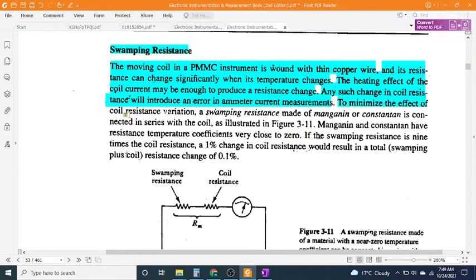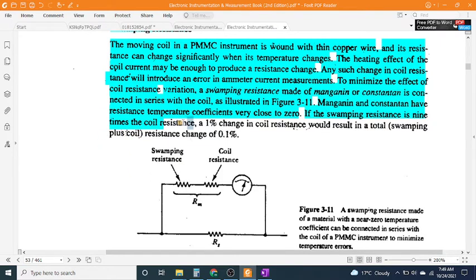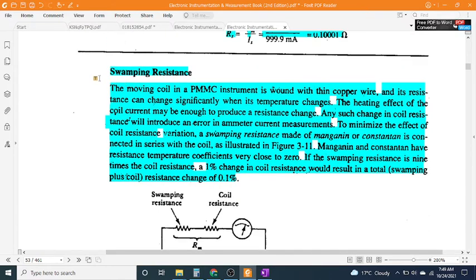To minimize the effect of coil resistance variation, a swamping resistance made of manganin or constantan is connected in series with the coil, as illustrated in Figure 3-11. Manganin and constantan have resistance temperature coefficients very close to zero. If the swamping resistance is 9 times the coil resistance, a 1% change in coil resistance would result in a total swamping plus coil resistance change of 0.1%.